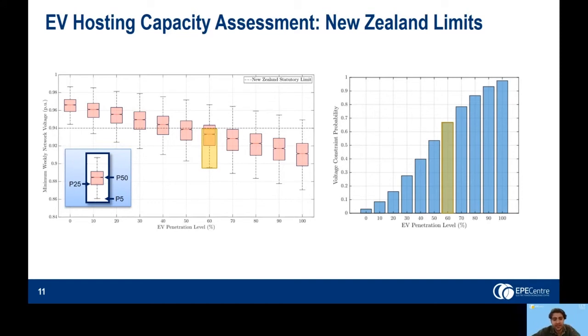It's worth noting that even at the 0% penetration level, there is a small chance of a voltage constraint. This is when temporal coincidence is high and load placements result in significant phase or feeder imbalance. On the other hand, at the 100% penetration level, almost all repetitions produce a voltage constraint.